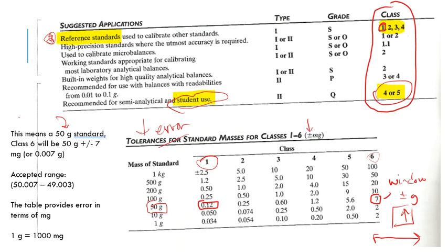So keep in mind, those are numbers in milligrams. So here, over here to the side, what you see is that it's the 50 gram standard. And if you look at class 6, that is 7 milligrams. So that's plus 0.007 or minus 0.007. So here would be the range that would be accepted for that particular standard weight.